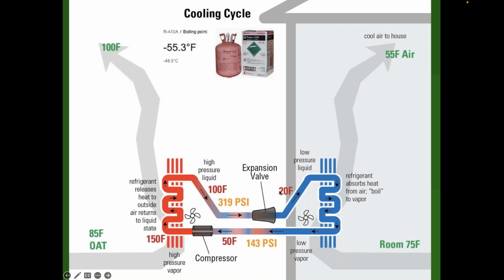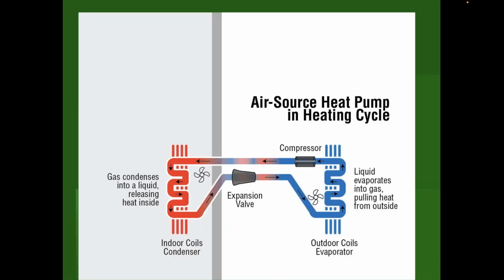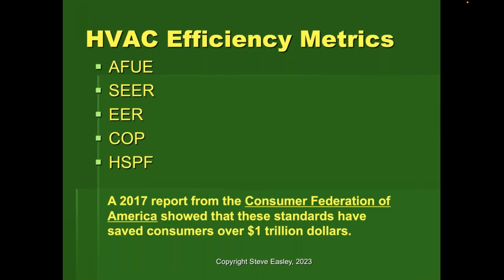We simply are taking this concept of boiling and compressing the liquid to really just move heat from one place to another. So heat pumps don't create heat. Air conditioners don't create cool, essentially. They basically just move that heat from one place to another. And so when we talk about a heat pump, all we do is add a reversing valve. And what that reversing valve does is reverse the cycle. So now we're taking heat out of the outdoor air and moving it to the inside of the house. And so that's simply how a heat pump works. It's a pretty simple, reliable process. And in today's units, they've certainly made tremendous strides in their efficiency and performance.